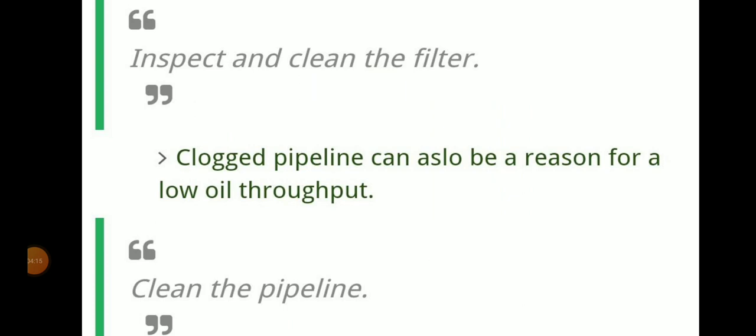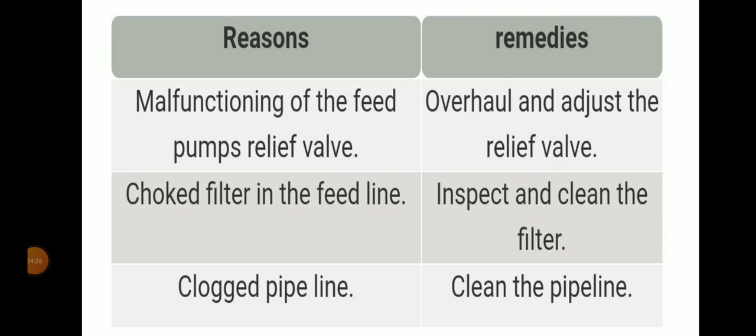Then a clogged pipeline can also be a reason for low oil throughput. So we need to clean the pipeline. So the reasons and remedies: malfunction of the feed pump's relief valve.